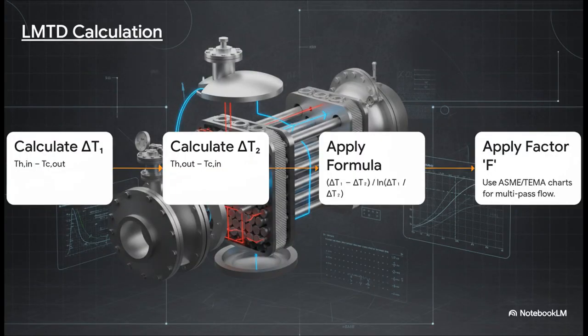Okay, so the calculation itself? It's a four-step deal. First, you find the temperature difference at each end of the exchanger, then you plug those into the LMTD formula. But hold on, there's a catch. For those multi-pass designs like our BEU, the flow isn't just a simple straight line. To account for that more complex flow path, we have to apply a correction factor, F, which you can look up in standard TEMA charts. That gives us our true corrected temperature difference.